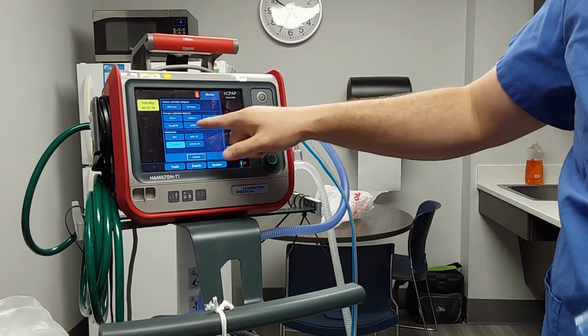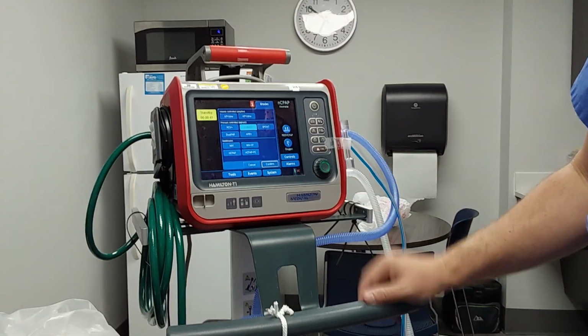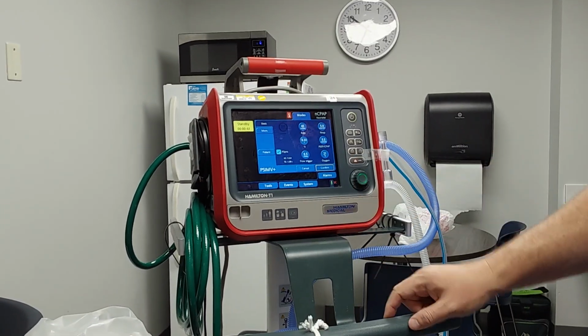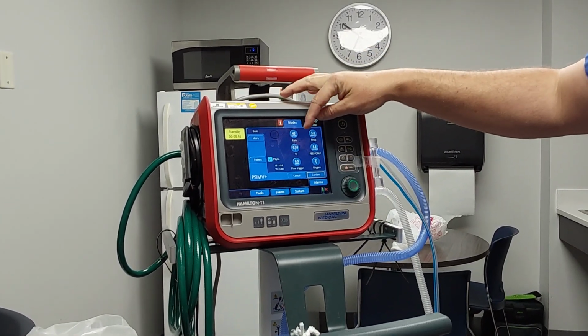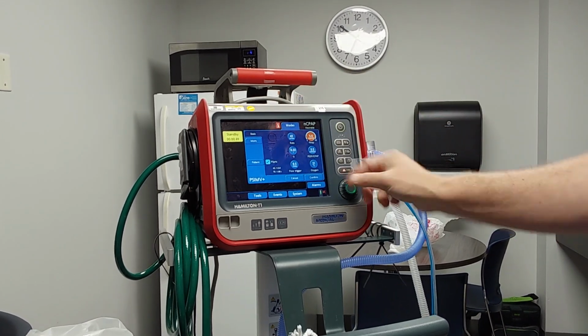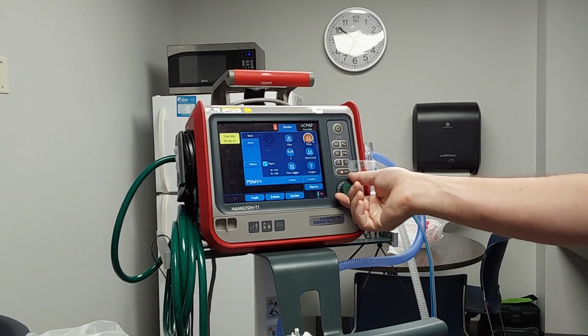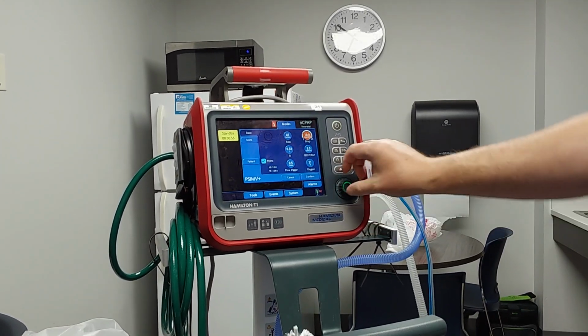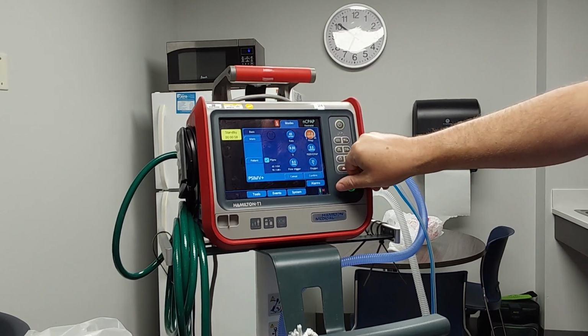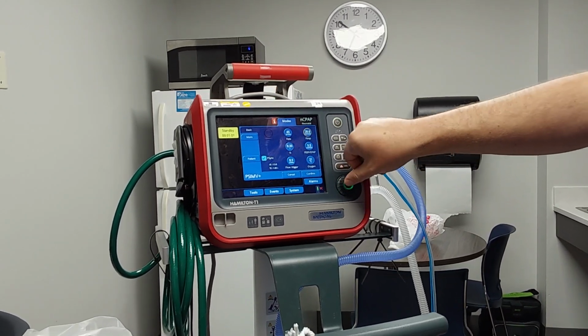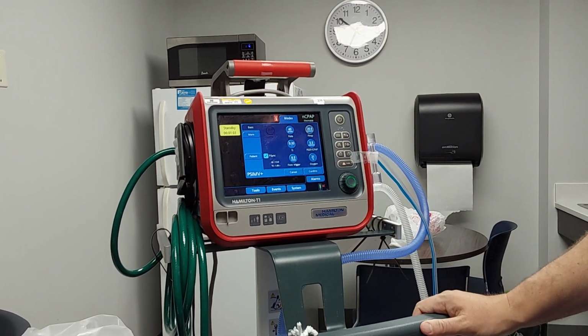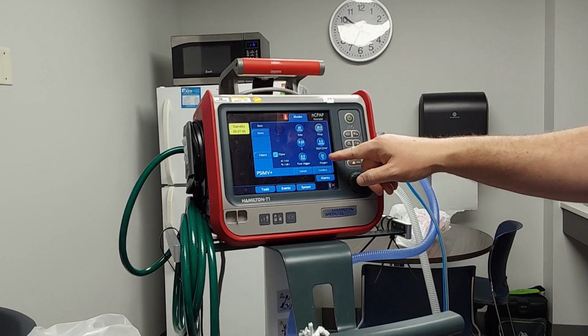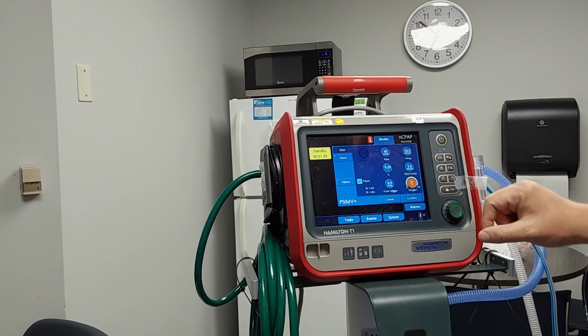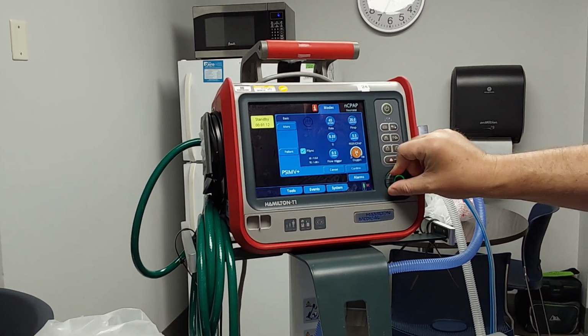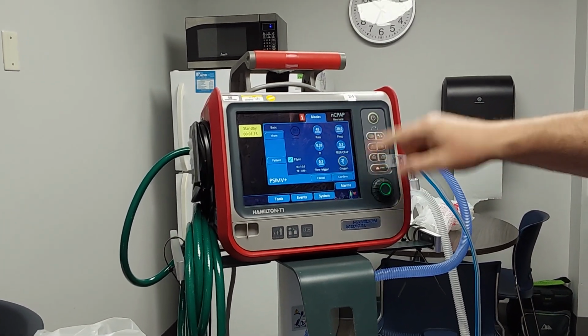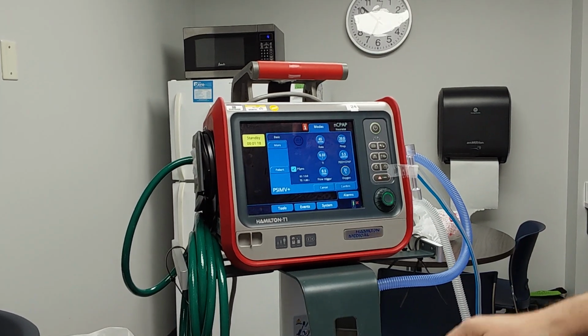And then change your mode. Normal mode for Neos is going to be pressure SIMV. Inspiratory pressure, we're going to go up, so I would probably start at around 20. All of the other stuff is fine. You're probably going to need more than 21%. I would start between 30 and 40 on a ventilator, yeah. But I'm going to leave it at 21 right now because we're not plugged in to O2.